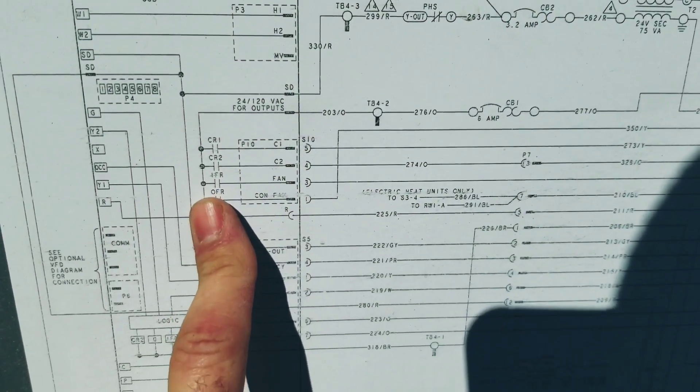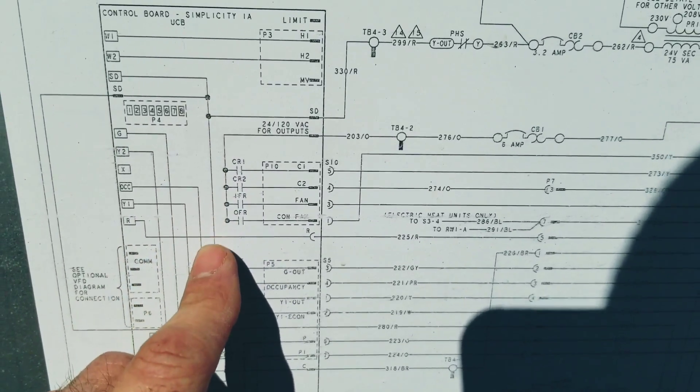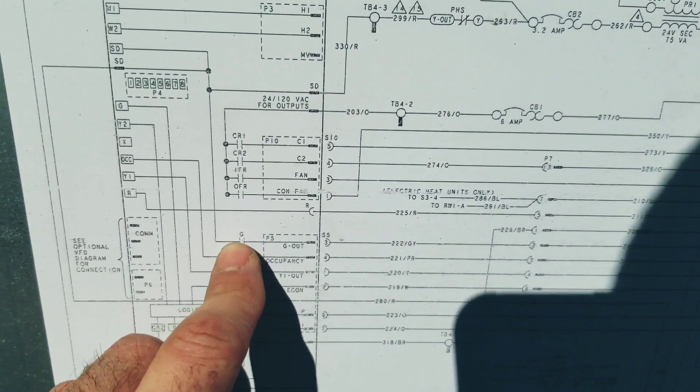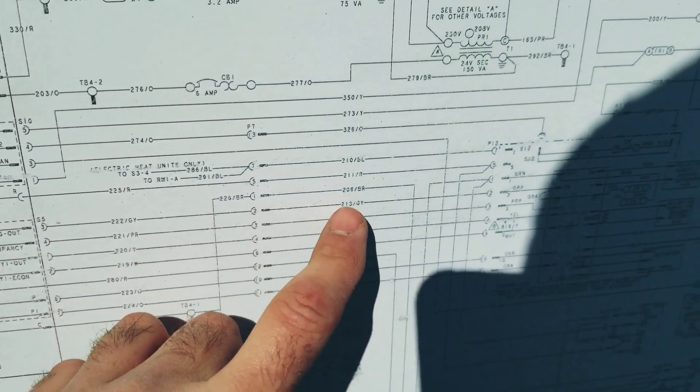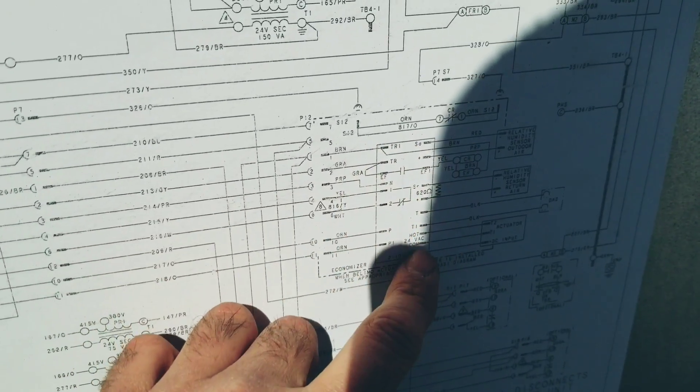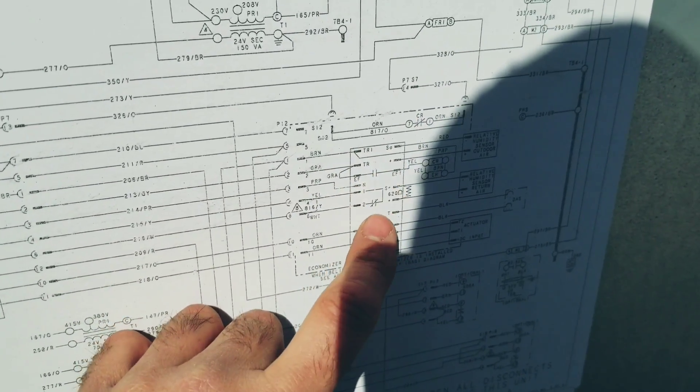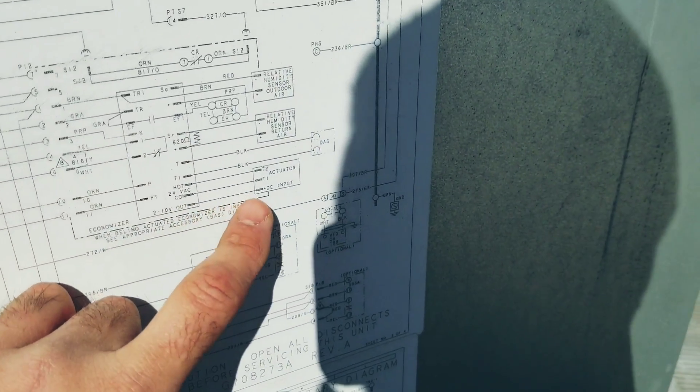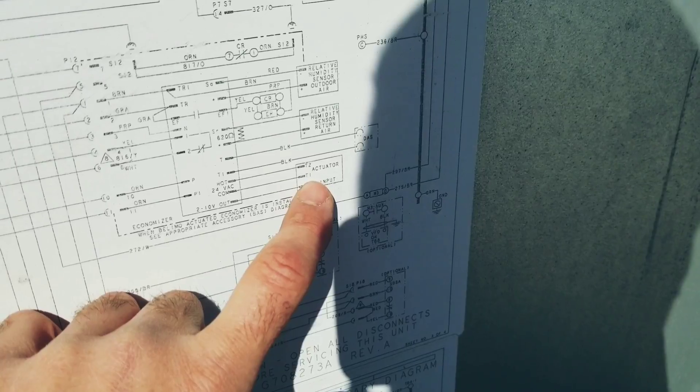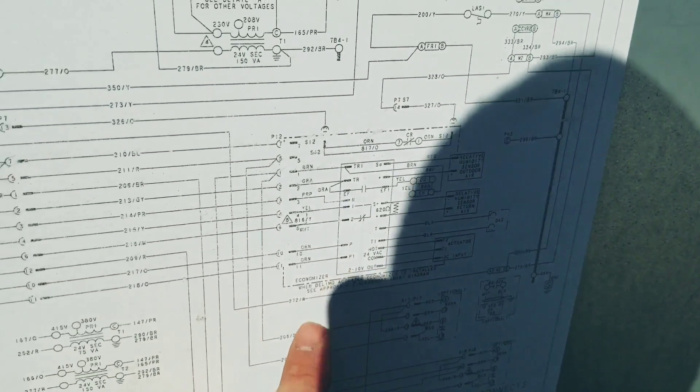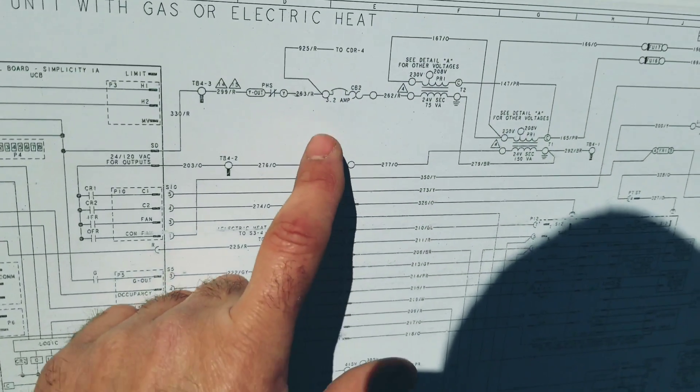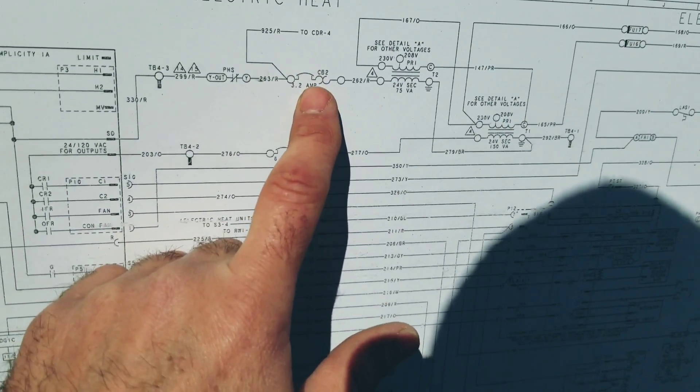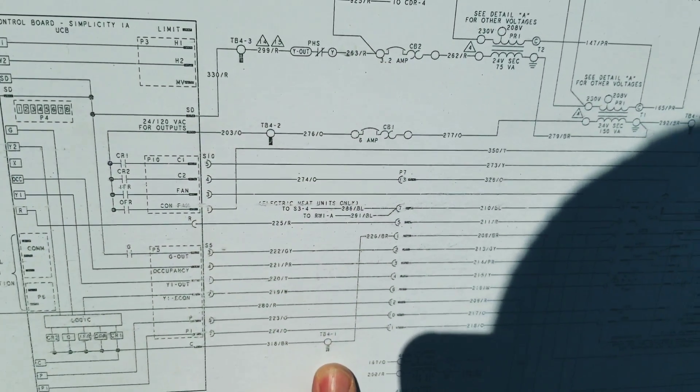The other one, if we follow again through this circuit here with the normally open G contact, goes over and powers up the economizer board and anything that the economizer board takes power from. We have a motor in there—an actuator. We're also powering up that actuator. So those are the three main loads on this that we're going to have to look into to find out why this tripped and why we have this weird cycling of the fan.